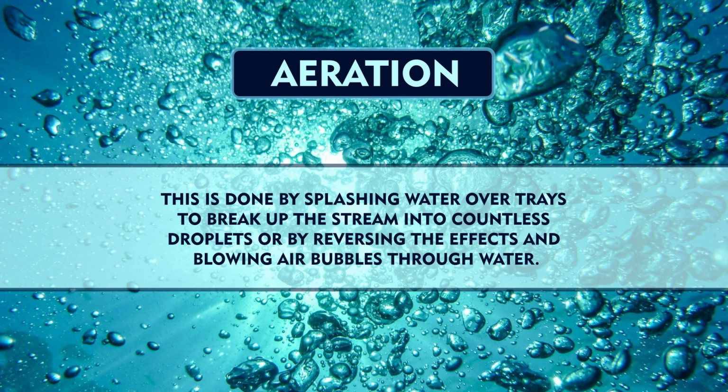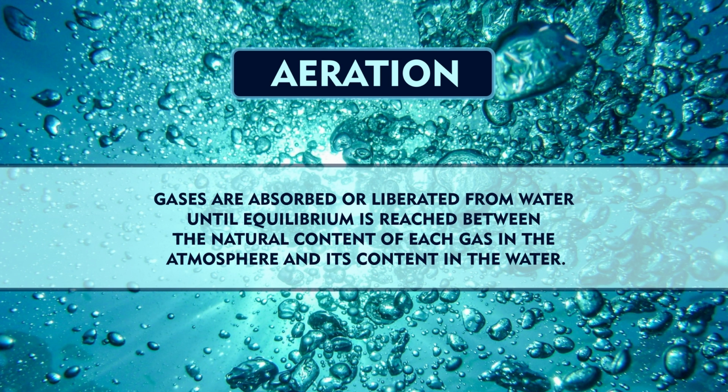This is done by splashing water over trays to break up the stream into countless droplets, or by reversing the effects and blowing air bubbles through water. Gases are absorbed or liberated from water until equilibrium is reached between the natural content of each gas in the atmosphere and its content in the water.